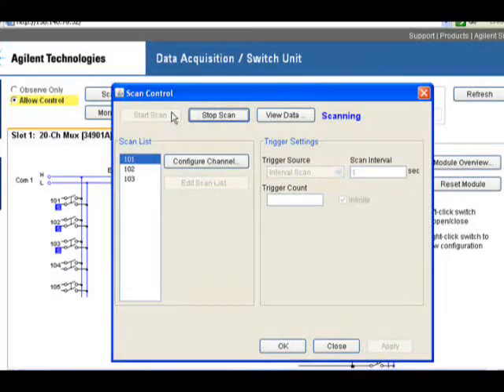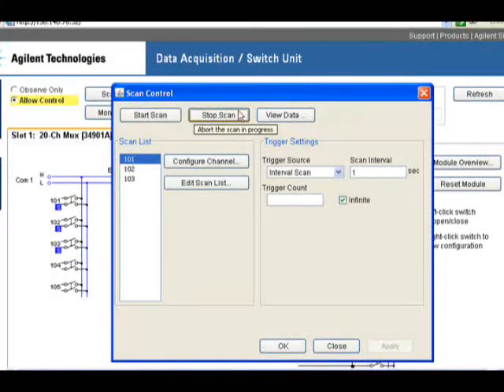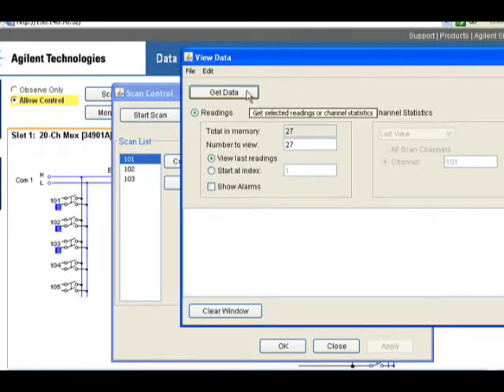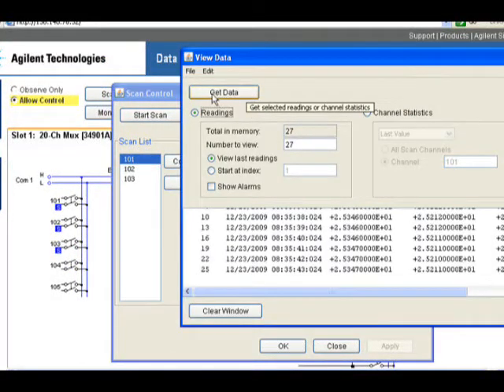Select the integration time and now you can copy the setup to multiple channels. Having set up the instrument, now you can execute scans and monitor results from anywhere on the network.